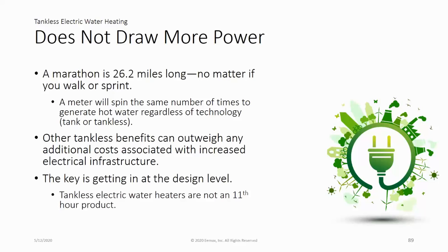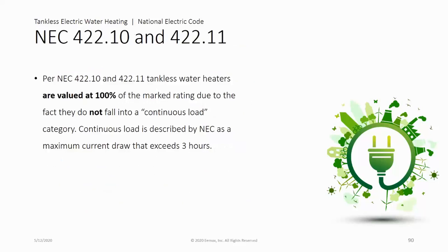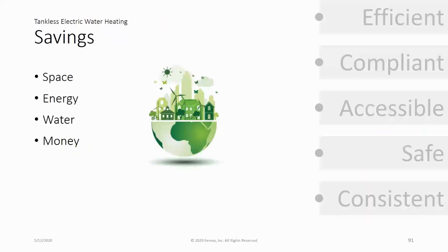So the challenge can be getting the right infrastructure. So always think tankless early in the equation to make sure you can support the infrastructure. Per NEC 422.10 and 422.11, tankless water heaters are valued at 100% of their rating. Therefore, you do not need to oversize the circuitry and breakers to 125%. Obviously, check your local codes.